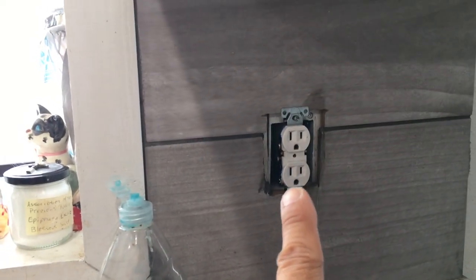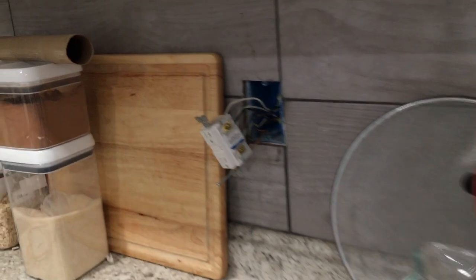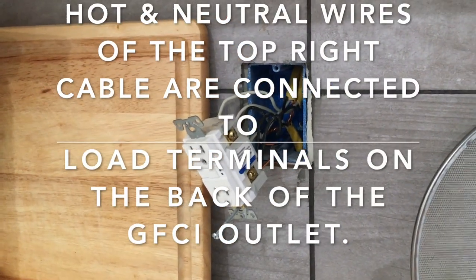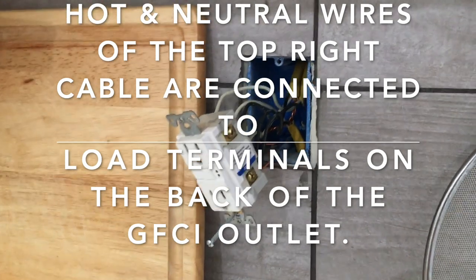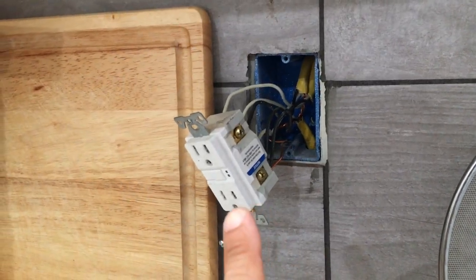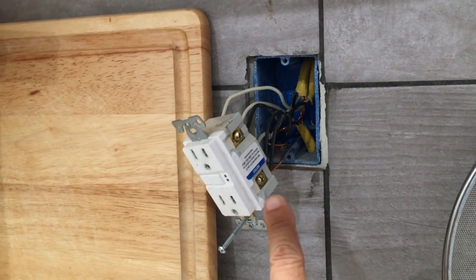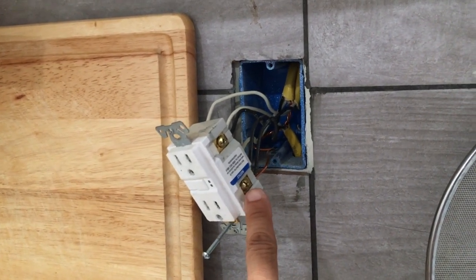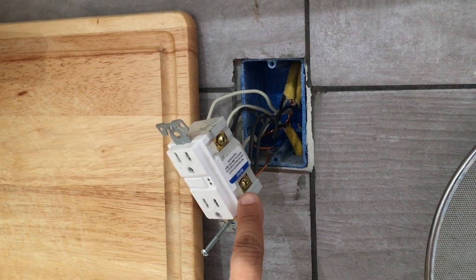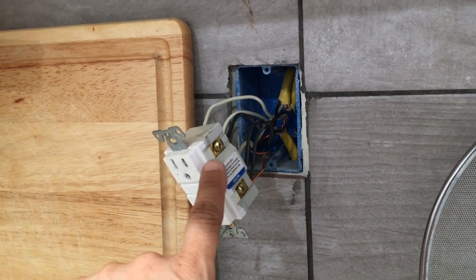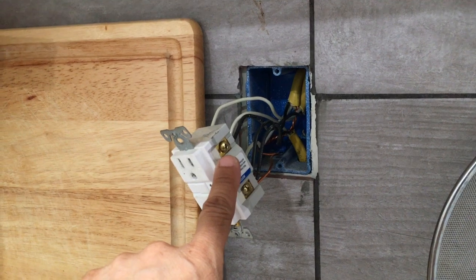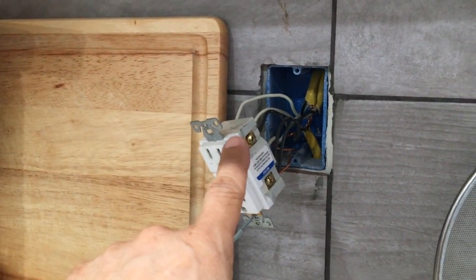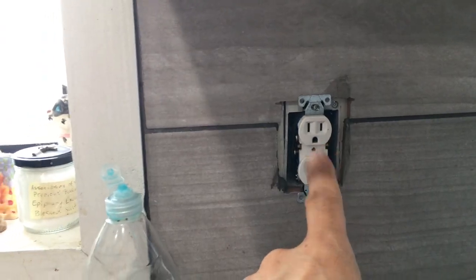Now, on our right side, this ordinary outlet is being powered by the load terminals on this GFCI outlet. Because the ordinary outlet on the right is connected to the load terminals on this GFCI, if that outlet experiences a ground fault condition, this GFCI will detect it and cut off power not only to itself but to the outlet on the right, giving you GFCI protection at that ordinary outlet even though it's not a GFCI itself.